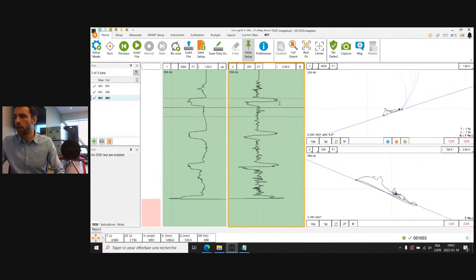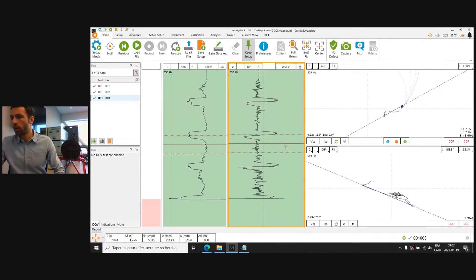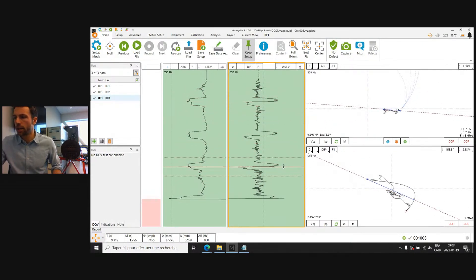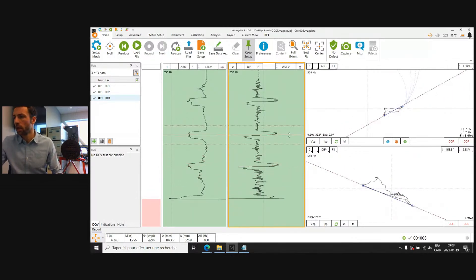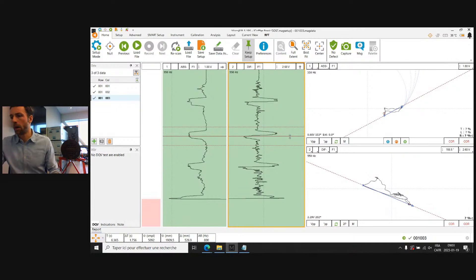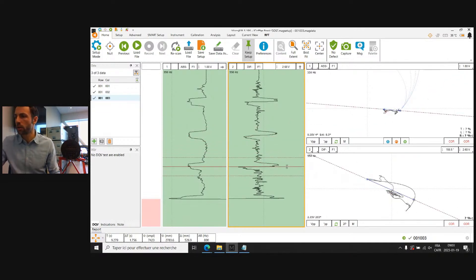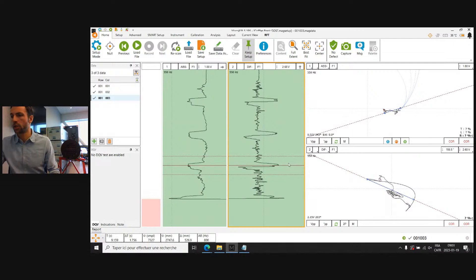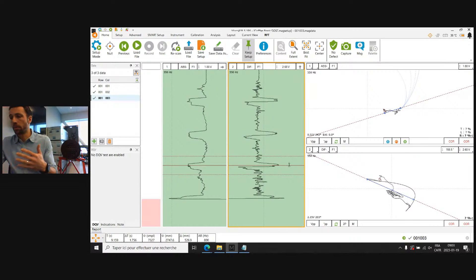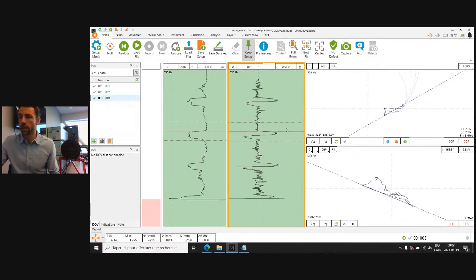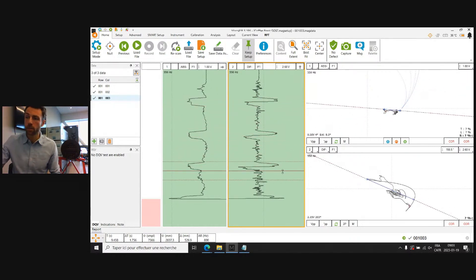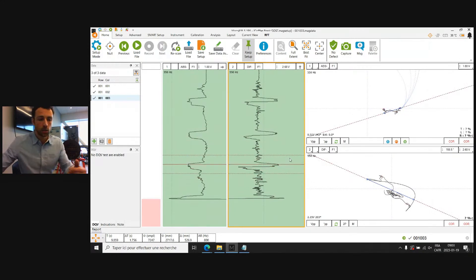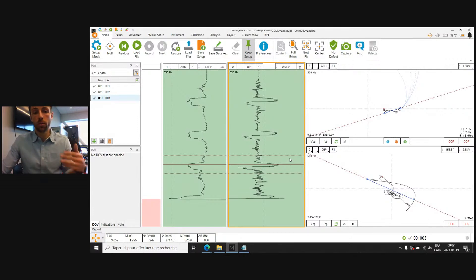We see clearly on screen the typical display — absolute and differential. I like to work with the voltage plane. Looking at our support plates, they're very consistent in their representation. The defect is located here, but currently there is very little information indicating a big indication right next to it. Sometimes there's a signal difference in the support plate, but this could easily be interpreted as a thinner support plate.